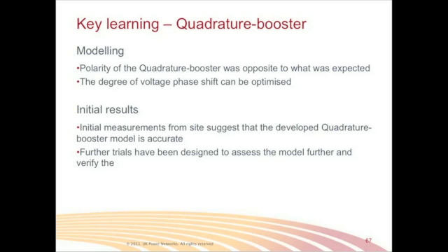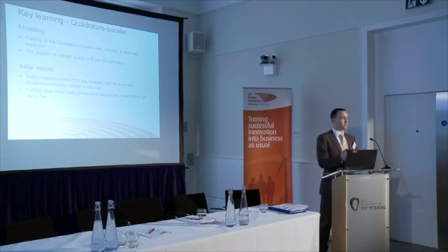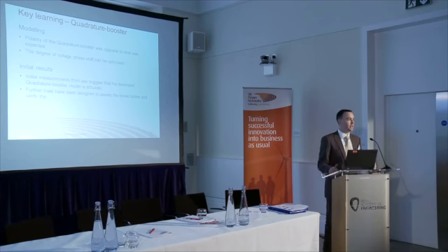So obviously, just to recap on some of the learning that we had, we heard that the quad booster was in fact boosting when it should have been bucking, which affected our initial modelling at the site. We've since rectified that and understand why that occurred. And as I mentioned, and so did Satiris earlier, for the next quad booster we would look to address that via tests, and then ongoing from there it would form part of our design review process.